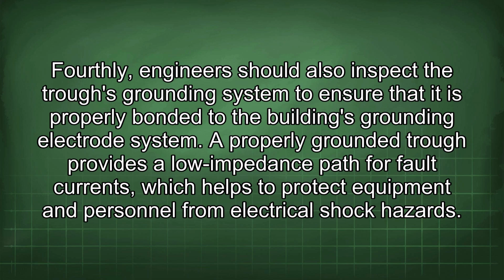Fourthly, engineers should also inspect the trough's grounding system to ensure that it is properly bonded to the building's grounding electrode system. A properly grounded trough provides a low impedance path for fault currents, which helps to protect equipment and personnel from electrical shock hazards.